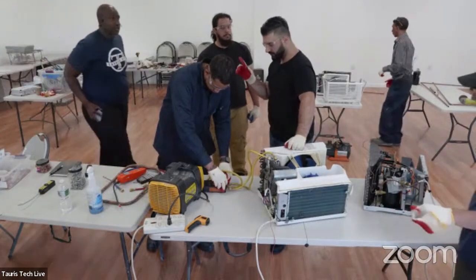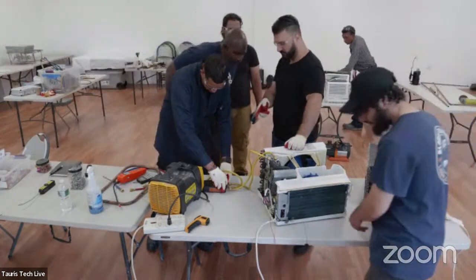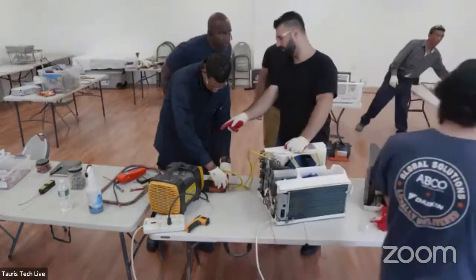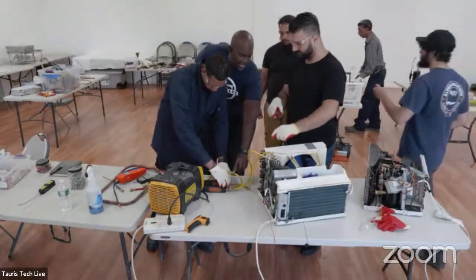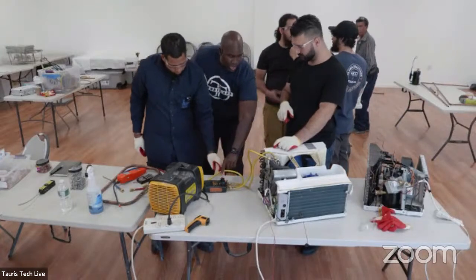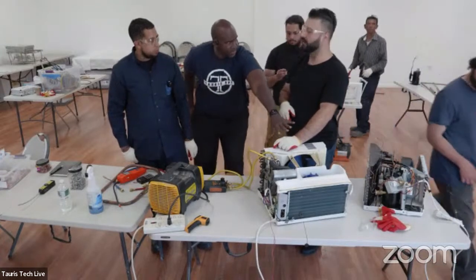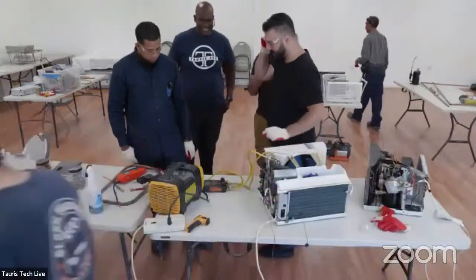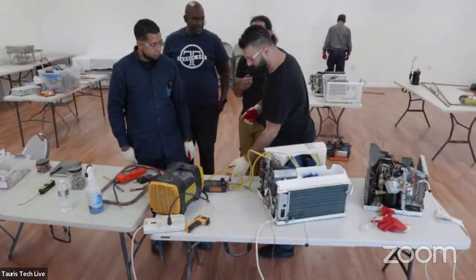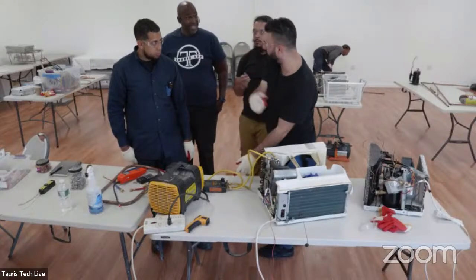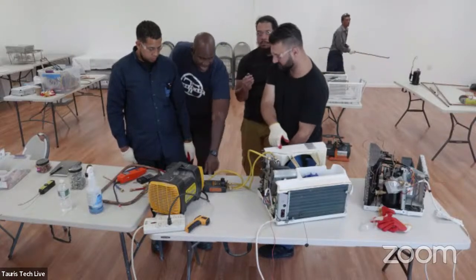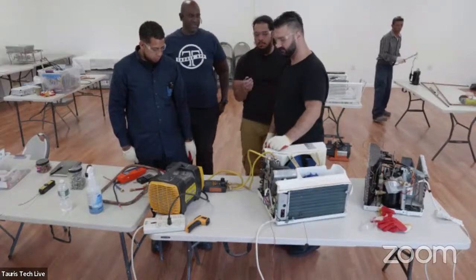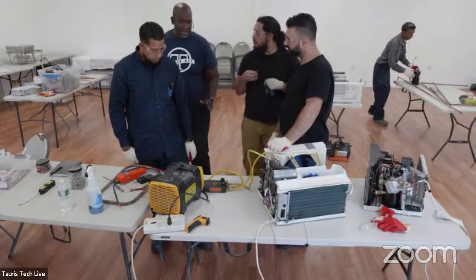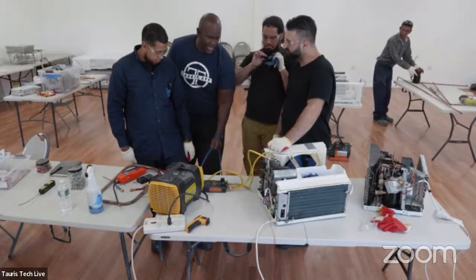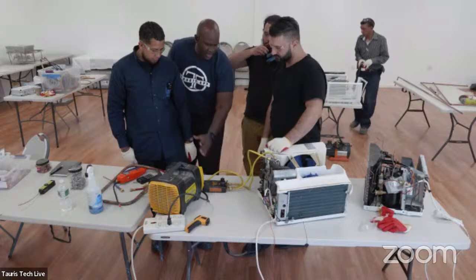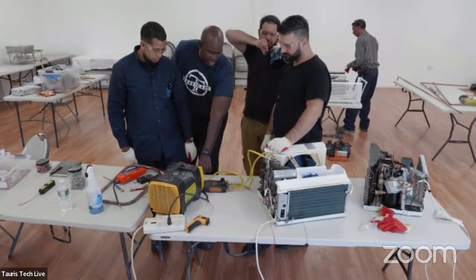So when we close the valve, does the vacuum go? It's just on this side. Yeah, when you close it, I'm just measuring this side — that's why. I couldn't understand because it should be a better vacuum in here than here. Yes, so if I put another gauge over here, that would be in vacuum too. But at the same time, on the discharge side, you feel it, it's warm, because it's discharging from the compressor and the condenser — there's a lot of refrigerant here.